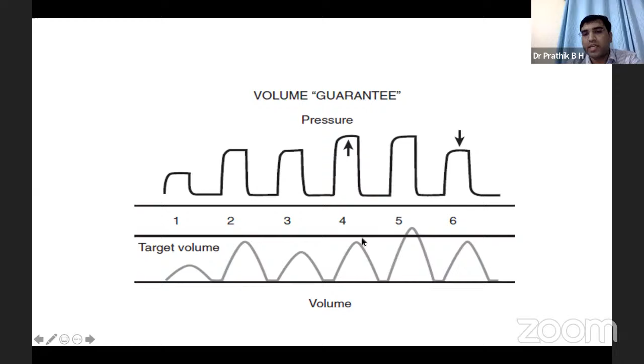But if there is any improvement in patient compliance, again there is an overshoot of tidal volume. So in breath number 6, you can see here, the ventilator again decreases the pressure to deliver the fixed targeted tidal volume. So basically here the pressure is changing or fluctuating to deliver the targeted tidal volume the clinician has set.